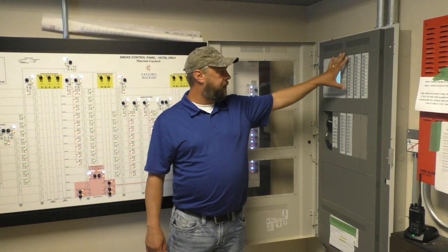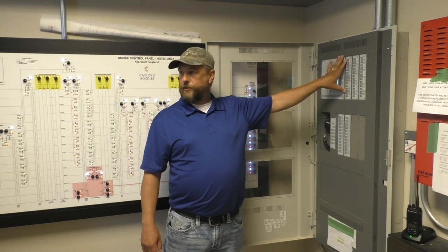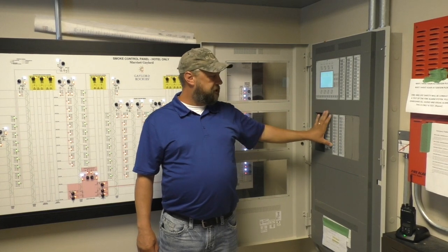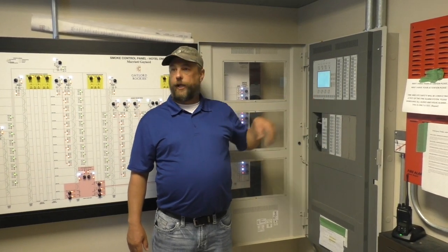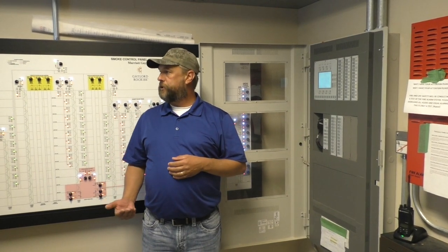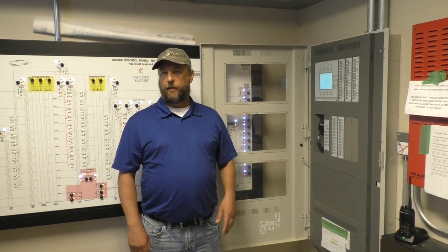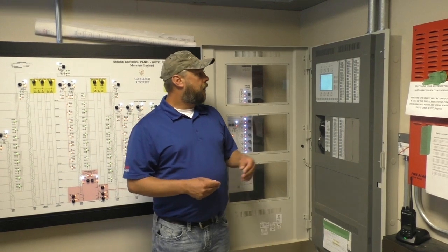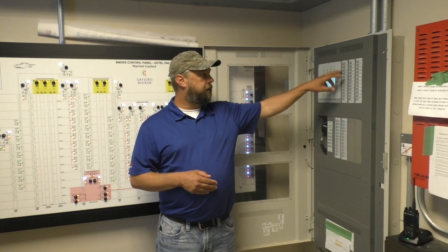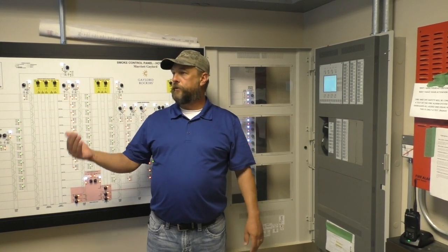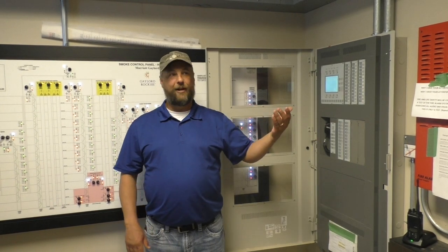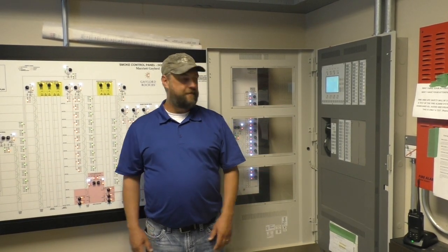This system is separated within your disables, as well as your floor paging, with hotel on top, convention center on the bottom. If you're in alarm, these disable buttons will not work. You have to clear the alarm first before you can disable any of the other functions. That being said, if you're out here and you're going to see some functionality, hit your disables first, then go through your function of smoking a detector, pulling a pull station, or running water flow. That way you're not evacuating a building at that time.